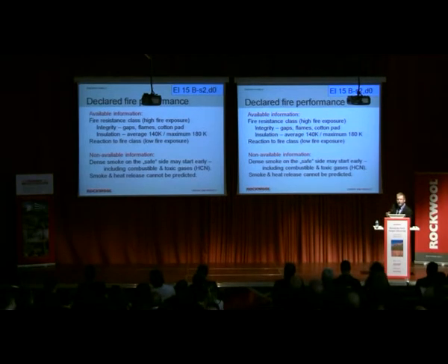But what we can't see on this classification is the dense smoke on the safe side, which may start very early, from the first or second minute. These gases are combustible. These gases may be highly toxic. And it's a fact that smoke and heat release in these kinds of products just can't be predicted. There is a big degree of uncertainty about what will happen in real life.